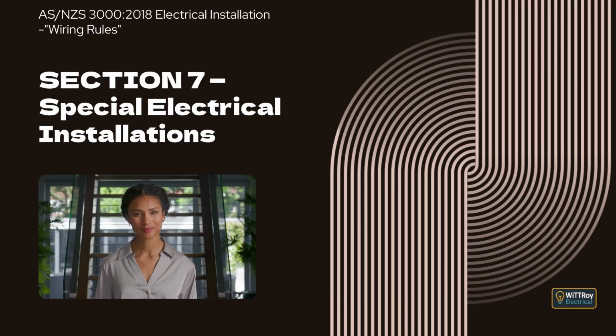Clause 7.2.3.3 Cables in the same enclosure. This clause explains that conductors for safety services must not be enclosed together with conductors for other safety services or other wiring systems. It then explains how separation can be achieved using divided ducts, compliant wiring systems, or physical separation within switchboards so that effective segregation is maintained.